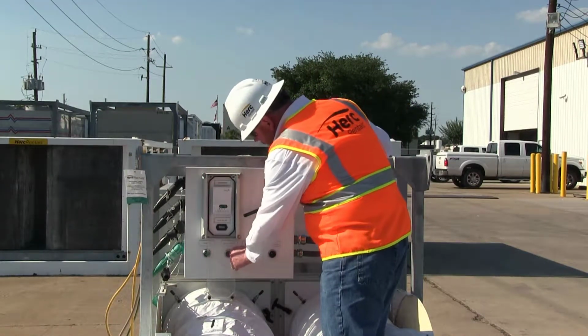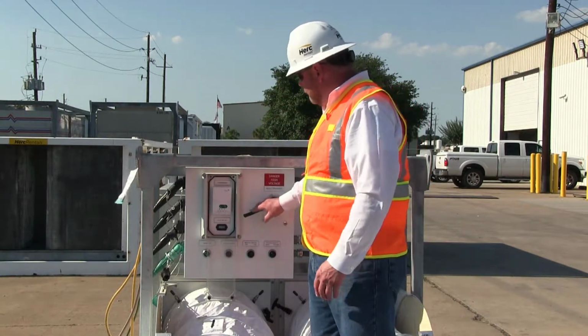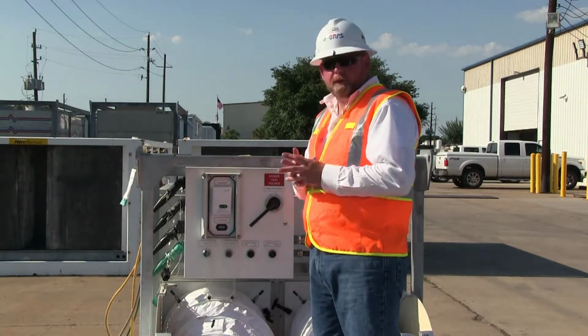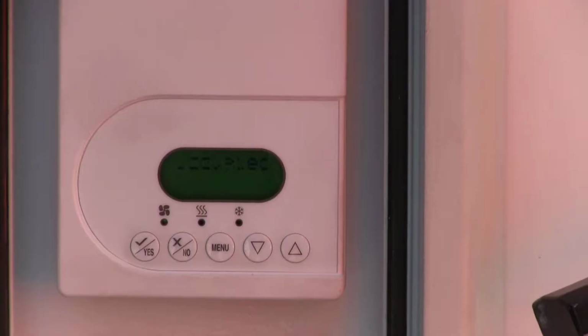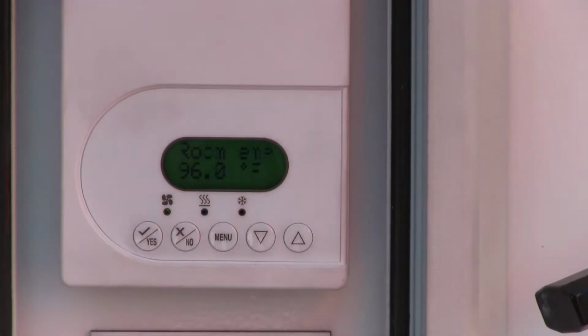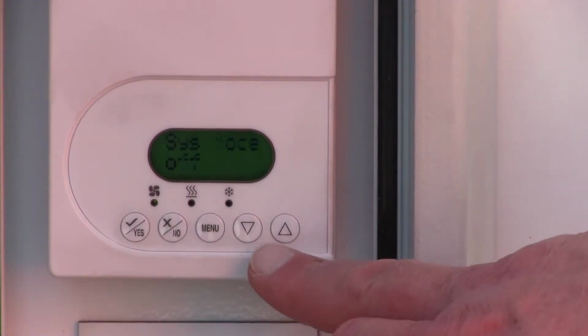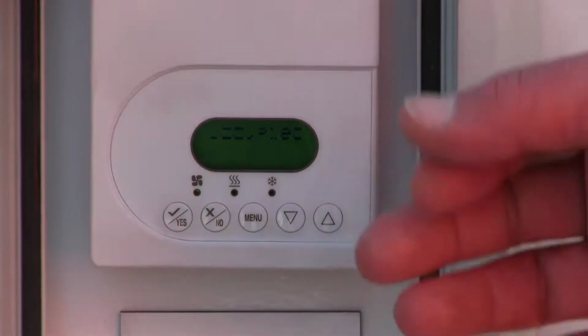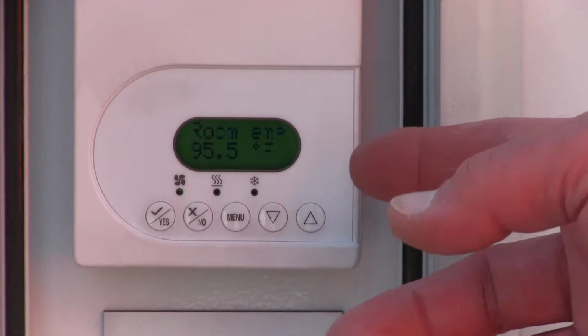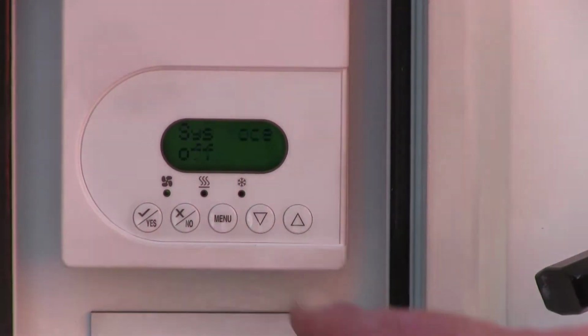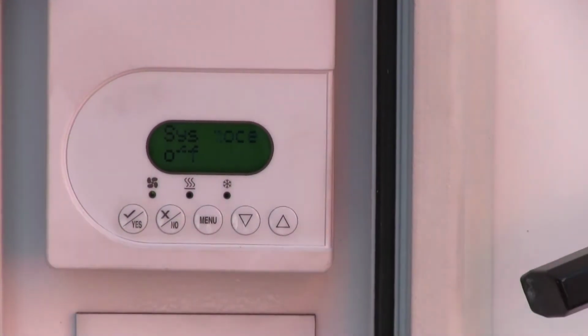It folds down, and we're going to let the system boot up here, and then we're going to go through the programming of the thermostat. Okay, now we've got our unit powered up. Our microprocessor now is powered to the thermostat. The thermostat's going through a scrolling marquee which says occupied. The room temperature is 95.5, and the system mode is in off.